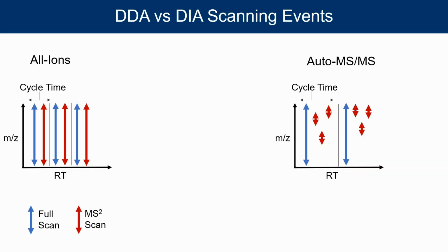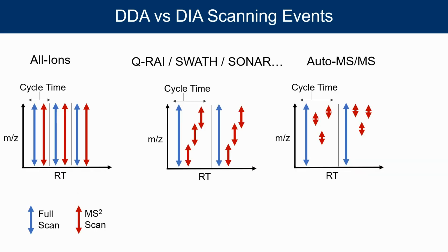And in that case, the most common approach is you use a full scan where you acquire all of your MS1 data or your intact molecules. And then following that, you get an MSMS scan, but instead of setting your quadrupole to select a single Dalton window for a single molecule, you set it to your entire mass range and fragment everything simultaneously. So now we can be greedy and grab everything out of all of those cups and see what we get.